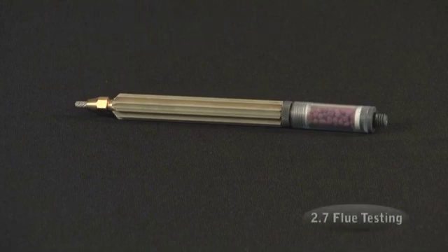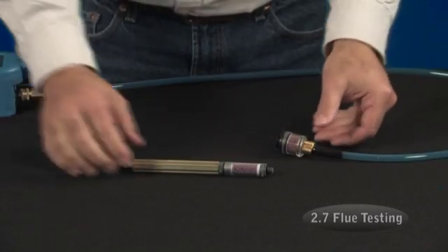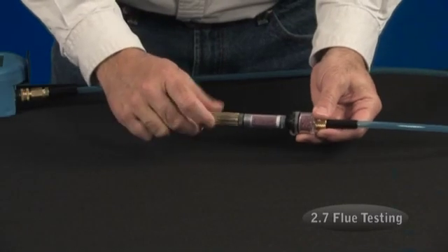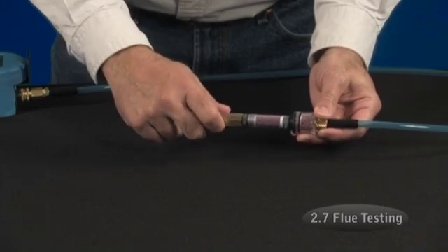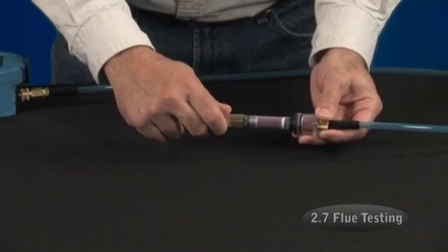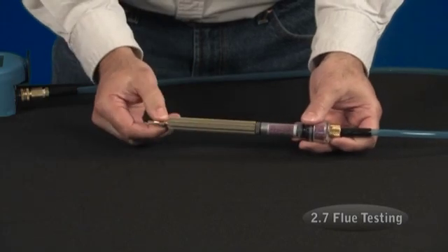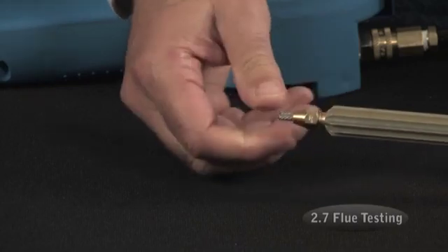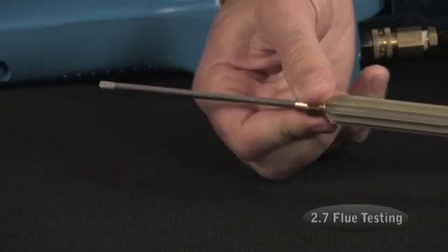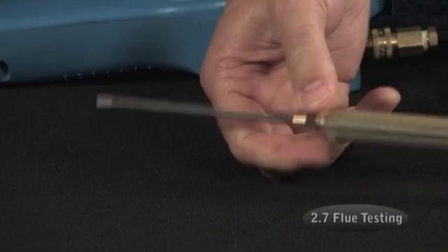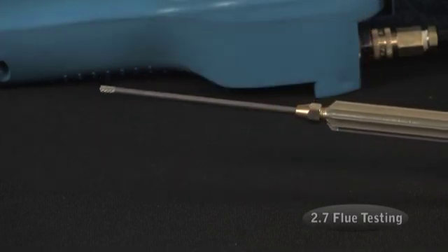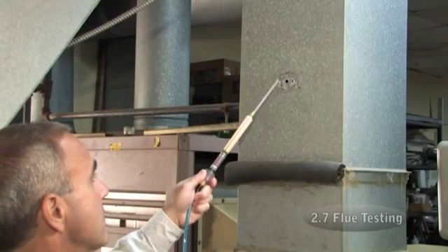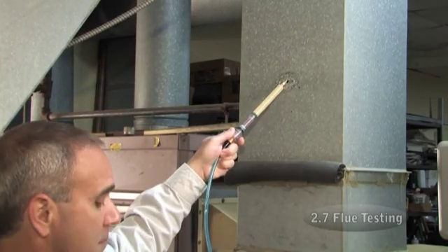To use the Explorer for flue testing, you will need a flue gas probe with an NOx filter. Attach the flue gas probe with NOx filter and dust and water block filter to the straight hose, the other end of which has the primary dust and water block filter, which connects to the Explorer. Loosen the brass collar in the front of the flue probe, fully extend the retractable tip, and lock it into place by tightening the brass collar. Then, position the tip of the probe into the flue of the heat exchanger.